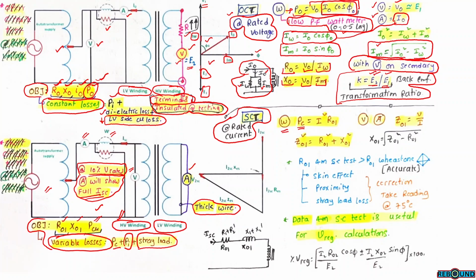The wattmeter gives the total copper losses, along with the voltmeter and ammeter readings. From these readings, we obtain the impedance Z01 equals V by I. From the wattmeter reading, R01 is obtained. From these two results, X01 is calculated. X01 equals under root Z01 square minus R01 square. This is the vector diagram. Short circuit current I2, and X02, I2, R02. This is the current and impedance triangle.